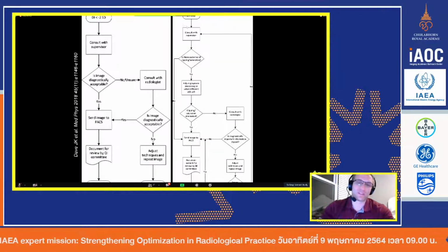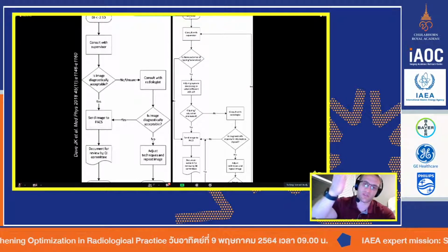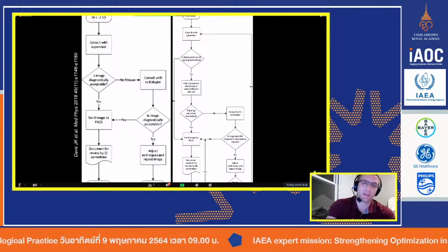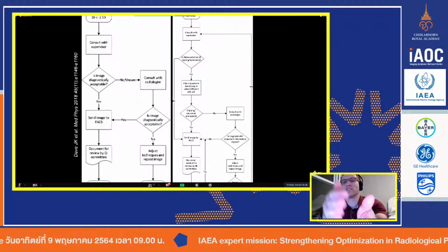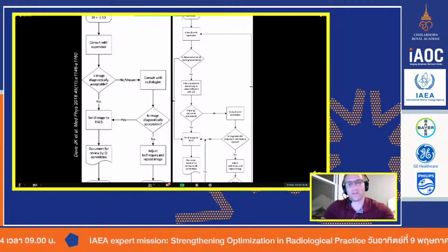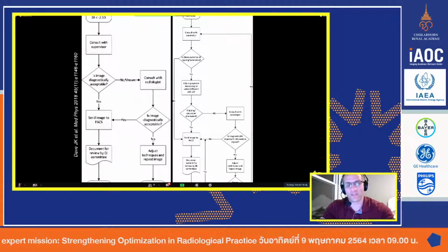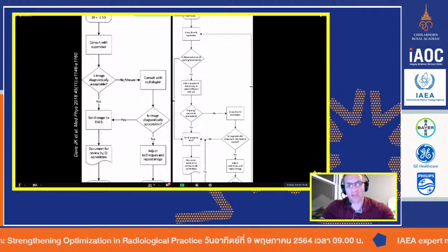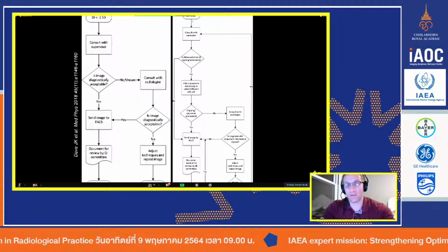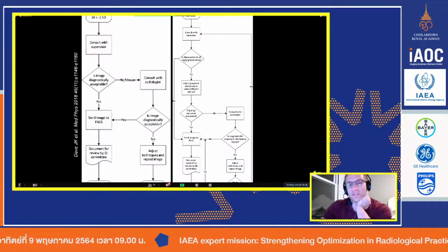And in a somewhat similar way, if the value was higher than 2 standard deviations, let's assume the upper standard deviation is 9. So the lower was -8 and the upper is say 9, and it's just written on a piece of paper in their control area. In this case, they call their supervisor again and they look at it. Now, over 2 standard deviations means it's going to be highly overexposed, so what you're looking for now is evidence of burnout and clipping saturation.